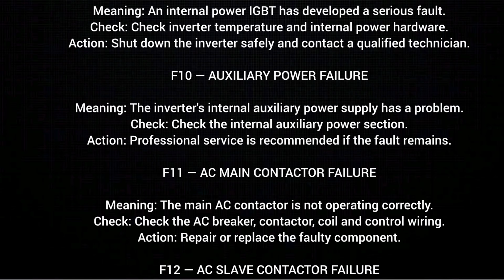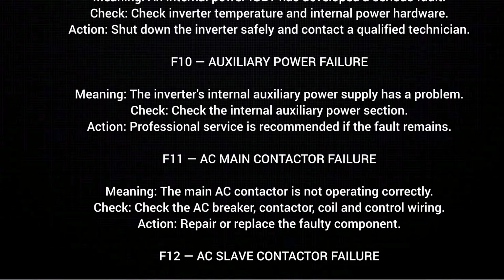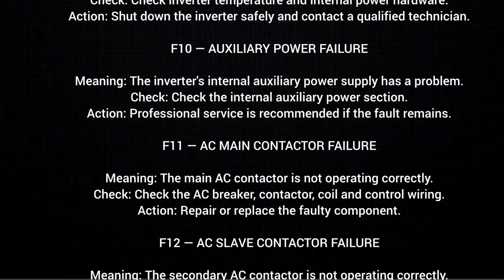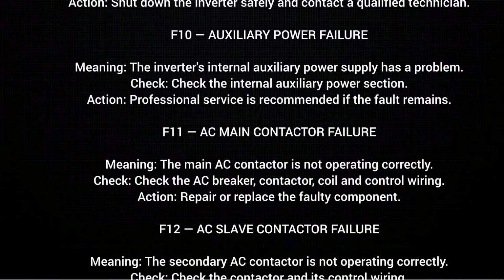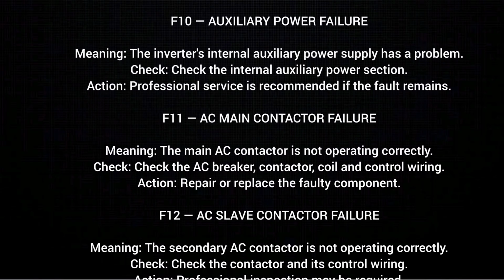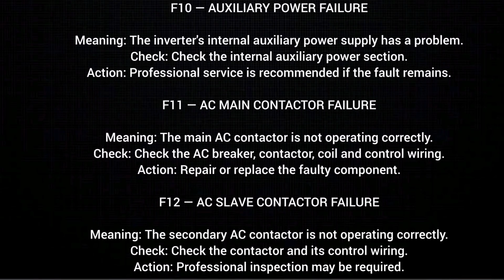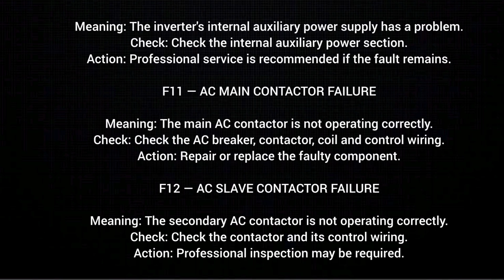F10 Auxiliary power failure, meaning the inverter's internal auxiliary power supply has a problem. Check. Check the internal auxiliary power section. Action. Professional service is recommended if the fault remains.